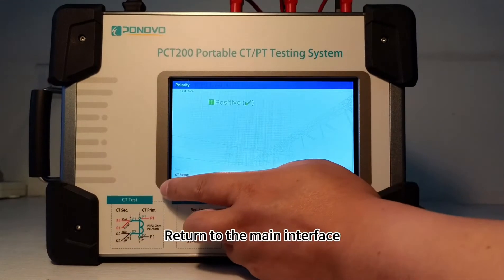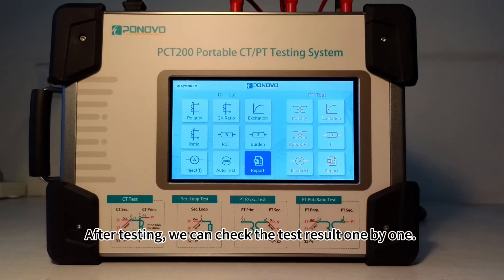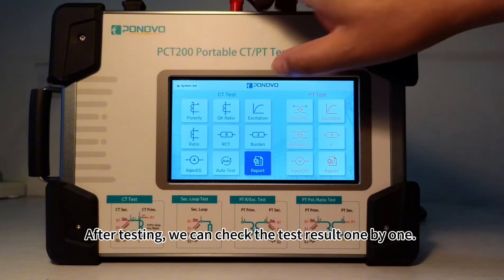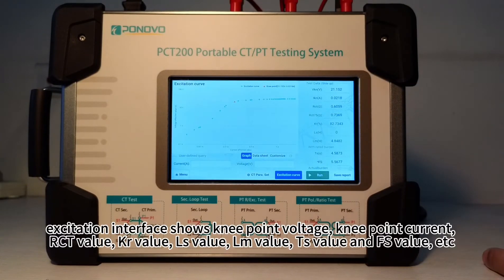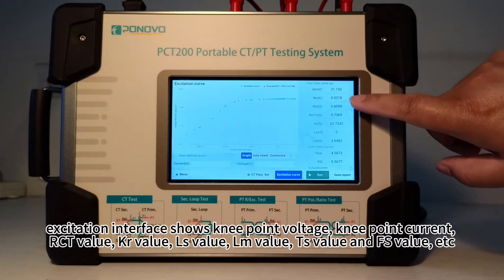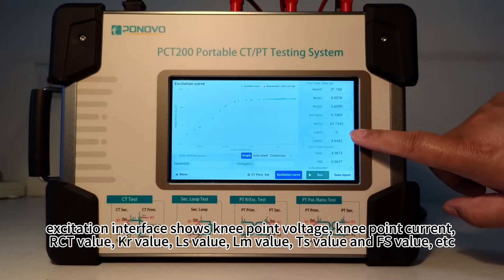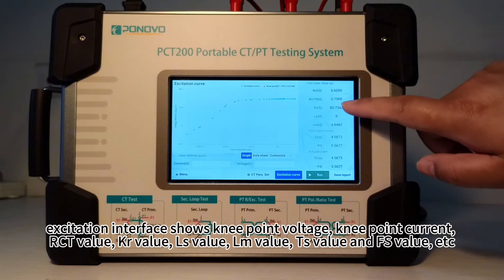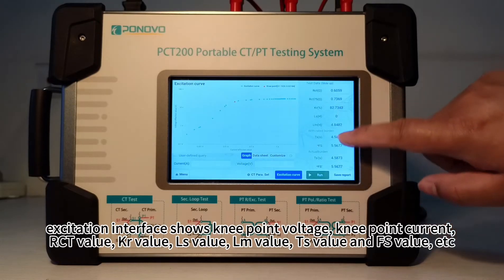Return to the main interface. After testing, we can check the test results one by one. Click the excitation window — the excitation interface shows knee point voltage, knee point current, RCT value, KR value, LS value, LM value, TS value, and FS value.